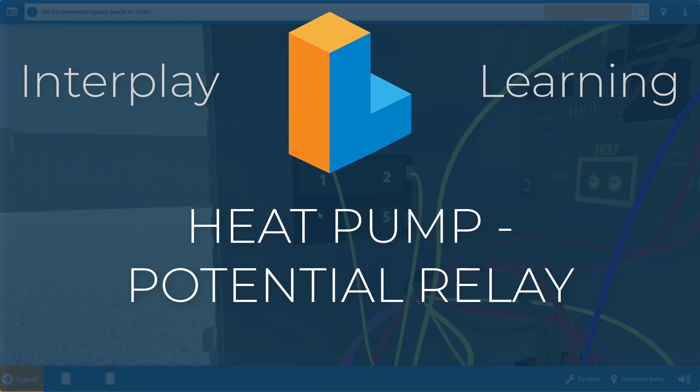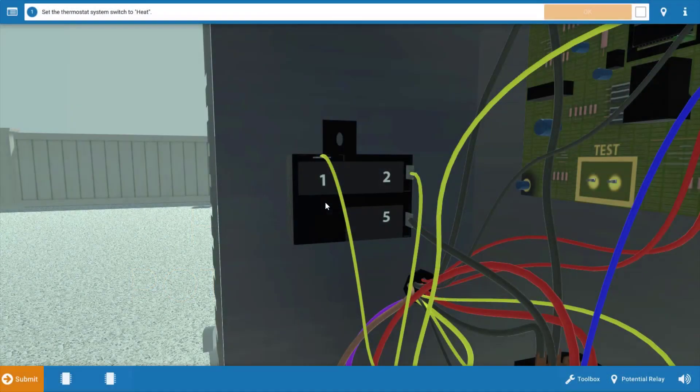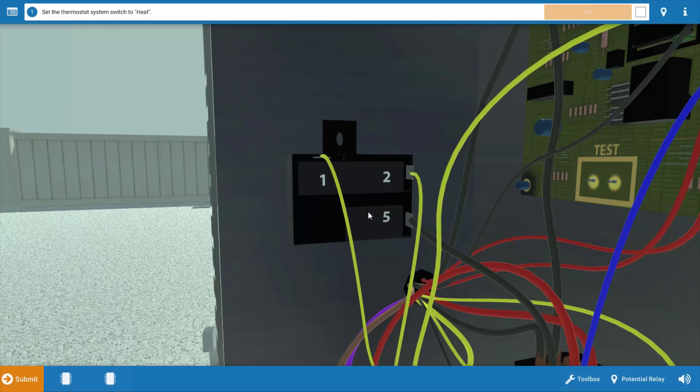Now, this is the potential relay right here. It has three active terminals: one, two, and five. Between terminals two and five are a coil that, when energized, will open a set of normally closed contacts between terminals one and two, and these contacts are in series to the start winding as well as the start capacitor. So what this is essentially doing is removing the start capacitor from the circuit once the compressor motor has reached approximately 75 or 80% of its rated speed.